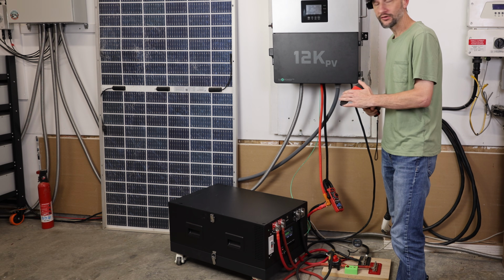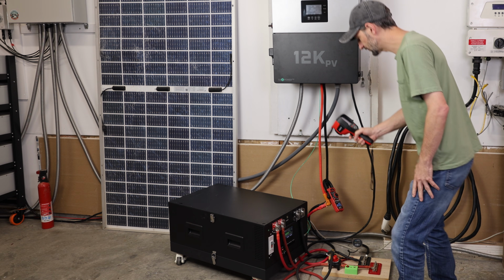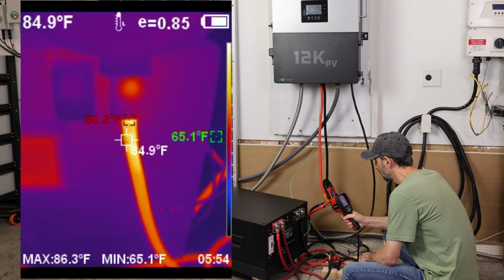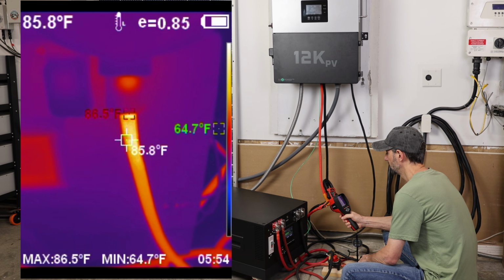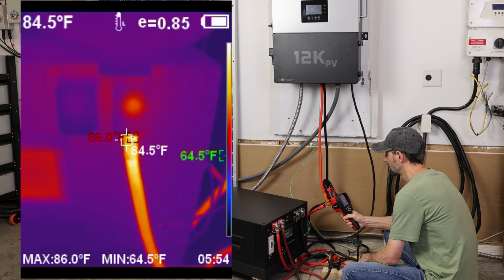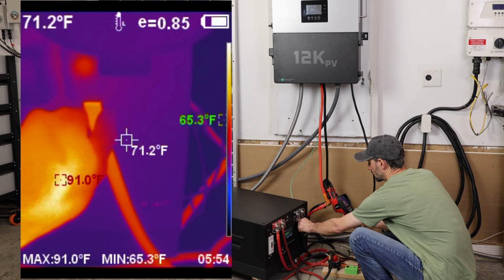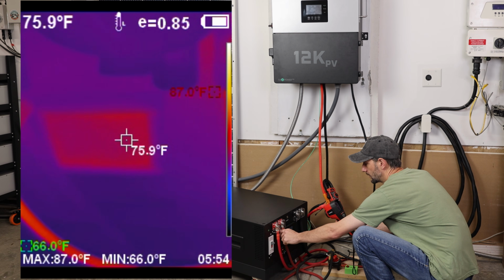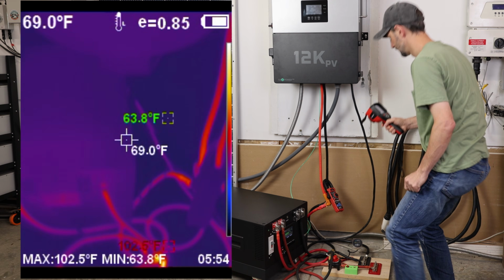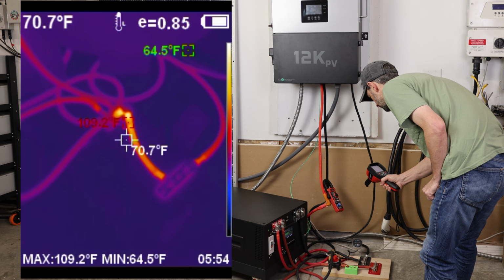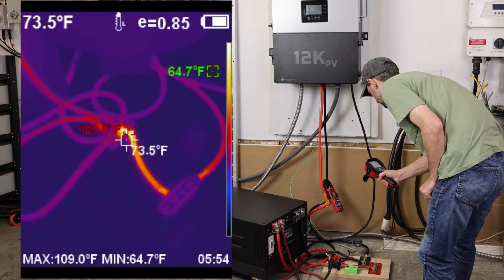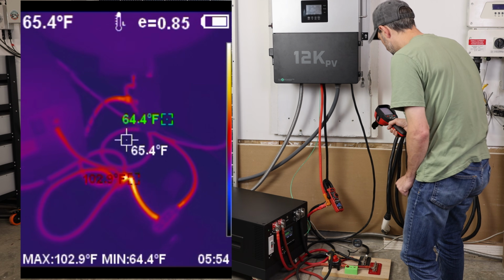Use the infrared camera here to take a look at what's getting hot. Right at the entrance here, we're getting a little bit warm, but not too bad. I have one 1/0 cable in there on my little test bench that's getting warm.